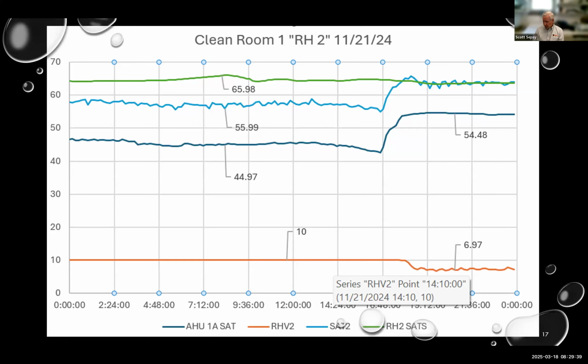So for equipment that seems to be operating at 180, we used our building automation system here, or data loggers, to trend the response to selected areas while supplying lower water temperatures. You set the supply water temperatures back slowly and see what happens. Hopefully, you will find that the terminal equipment can still meet the demands with cooler water. This test will reveal which units need a design for replacement or upgrade.